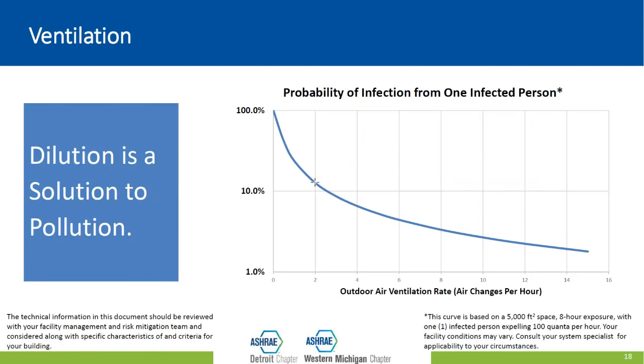Next slide. We need to get rid of that old air that we've breathed and coughed in and bring in some fresh, new, clean air. We call this dilution ventilation because it reduces the concentration of contaminants in the space. And when those concentrations are reduced, so is the probability that somebody else in the facility will get infected. This graph here shows how the probability of others being infected from just one sick person is reduced logarithmically when we increase ventilation rates. Now, it's never going to get to zero, but we can get it down to a reasonable percentage that we're comfortable with, right?